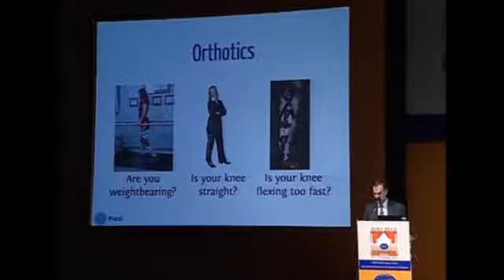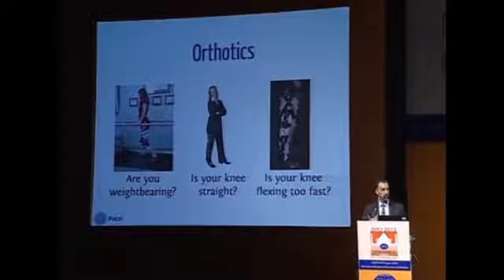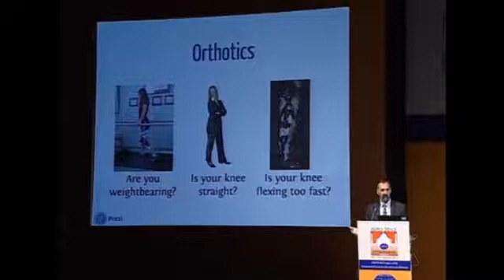Based on this decision, the device allows free knee motion at the appropriate time. New devices, such as the Ottobock C-Brace, make additional decisions and then control how the knee flexes during weight-bearing. Smaller and lighter devices can be made that use mechanical systems to engage only when the leg is straight, thereby trading off more complex control for devices that are smaller and lighter, even though they aren't able to engage during a stumble or when landing with a bent knee.